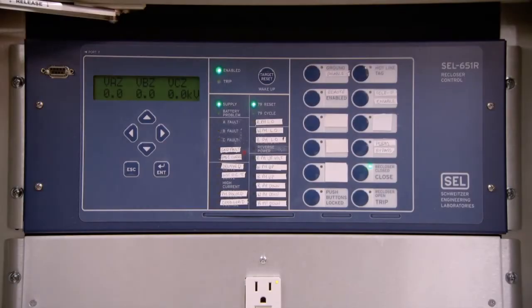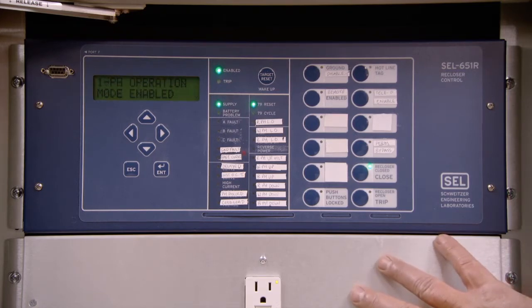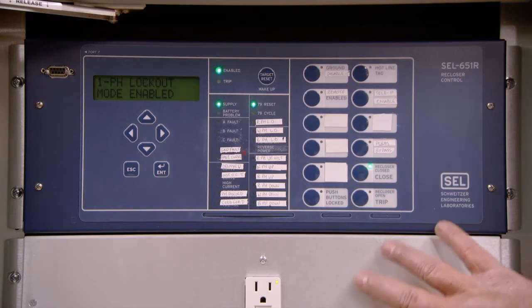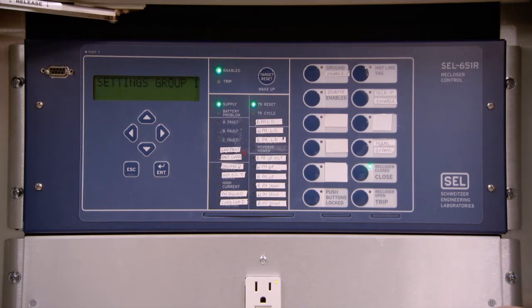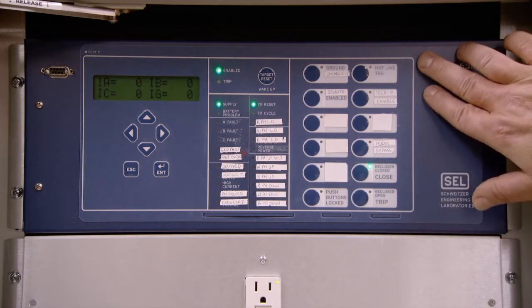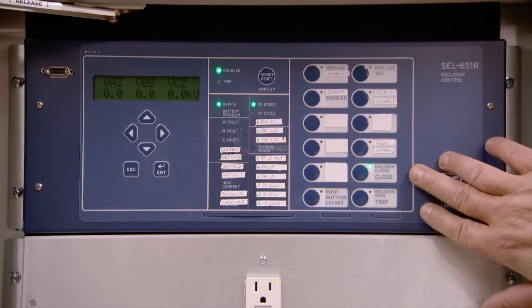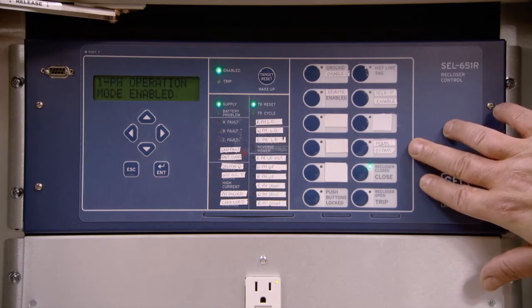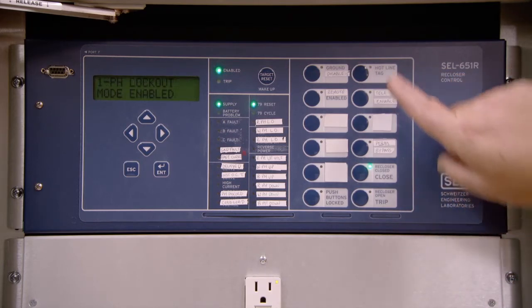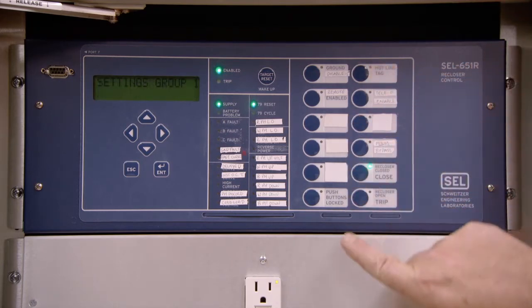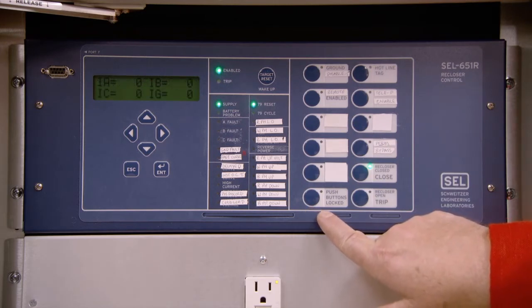This is an overview on the Schweitzer Engineering Laboratories 651R horizontally configured controller. It's the new standard controller that we are going to be using. It's paired up with a G&W Viper ST recloser. We'll talk about the recloser later on. All of the main control buttons are located on the right side of the controller. The trip, the close, permissive bypass, teleprotection, ground disable, remote enable, and push buttons locked.